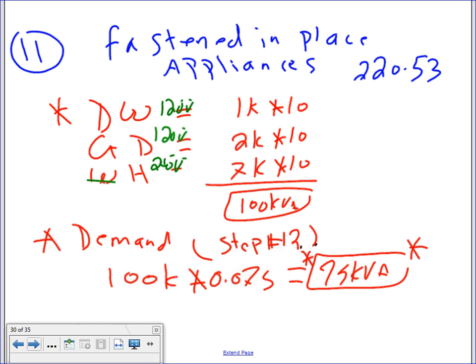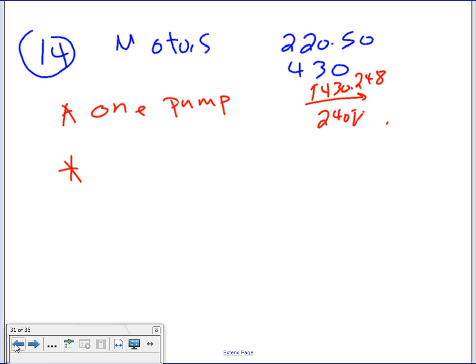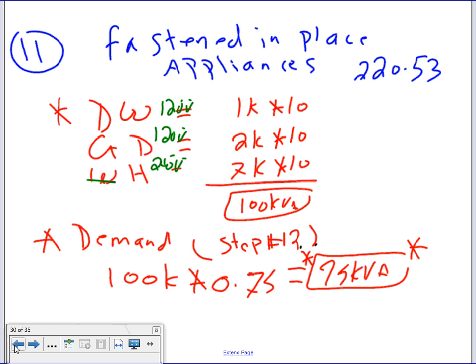Is it 75% or 7? No, 75 kVA. Oh, 75%. Oh, what the heck is that? That's not a 75%, chat. 0.75. Thank you. 75%. 4 or more, you cut them by 75%. Do we have 4 or more? Look at this. We have only 3, chat, but we have 10 of each. We have 30. Remember, Adam, when we were doing the apartment, well, we derated for the whole building. For the apartment, we did not derate because we don't have more than 4. Okay. Any comments, guys? Did they go fast? Slow down, chat. Makes sense? You use 75% if you have 4 or more.